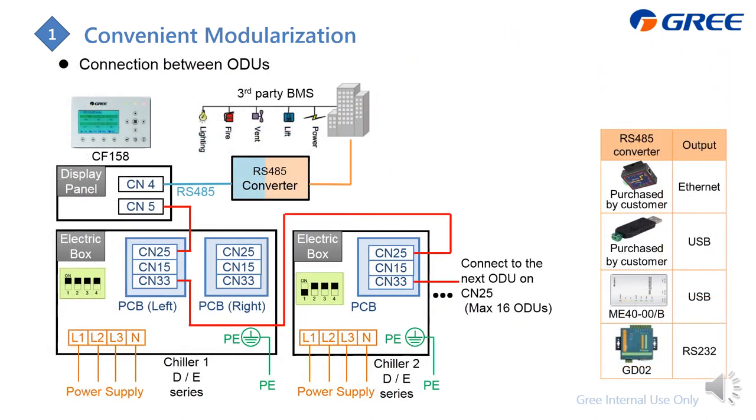For the on-off series, which is the D or E series, the wiring is similar, but the controller is different. You can identify it from the model — it will be CF158. There are two ports: CN5 connects to the chiller, and CN4 outputs the RS485 signal for BMS control.